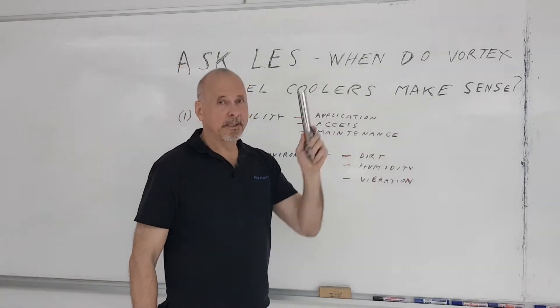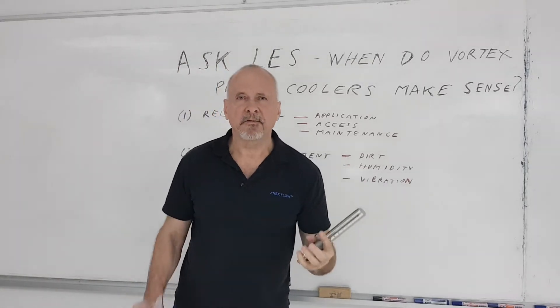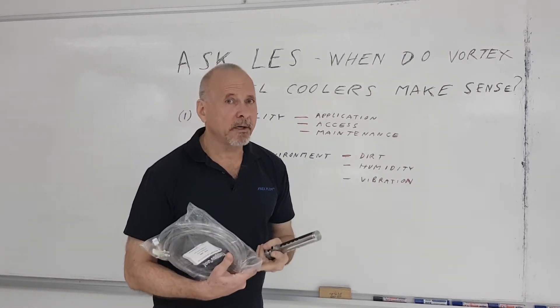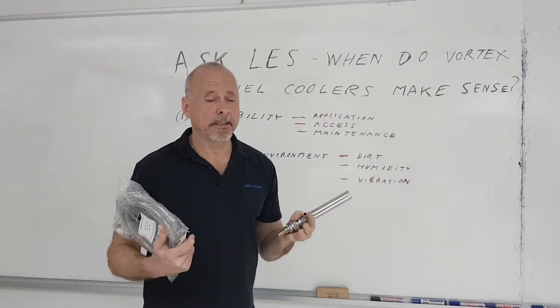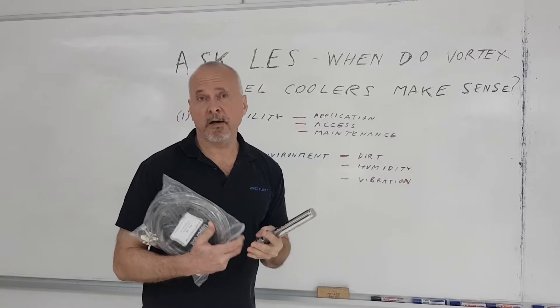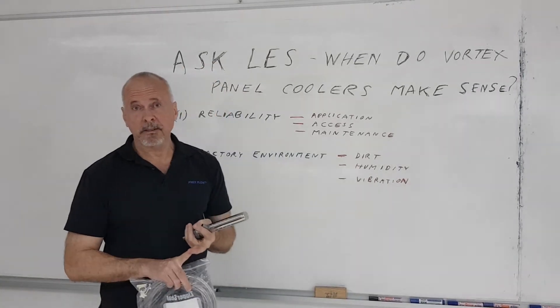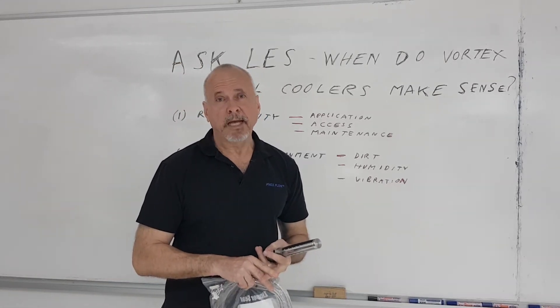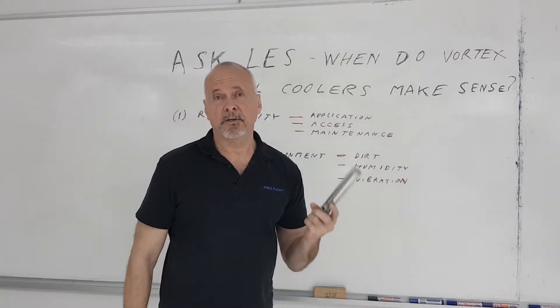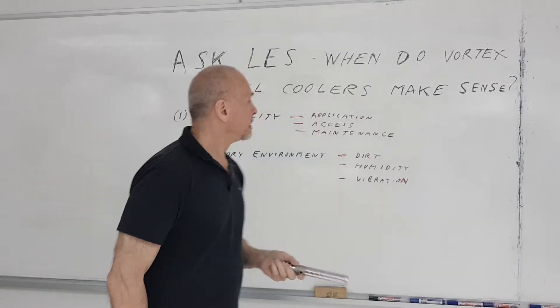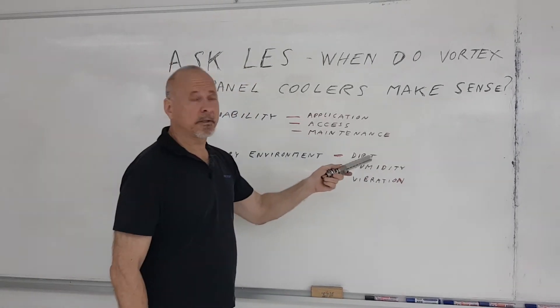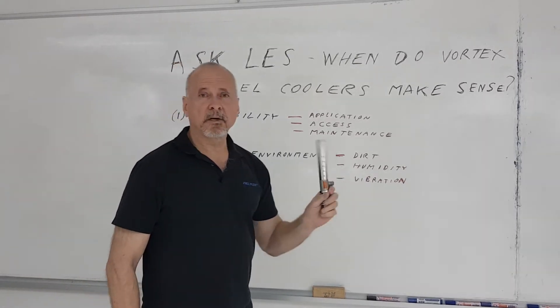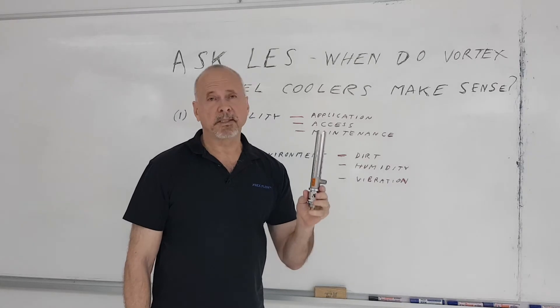Finally, vibration. If the factory environment has a lot of vibration spreading to equipment, that's going to affect the life of the air conditioner, meaning you'll probably have to replace the refrigerant — the CFC — far more often. Not only does that affect the environment, it's also an extra cost, downtime, and more maintenance. Those factors more than offset the cost of the extra energy required to operate a compressed air panel cooler. With the factory environment, consider the dirt, the humidity, and the vibration — the more all these occur, the more sense it makes to use a vortex tube operated panel cooler.